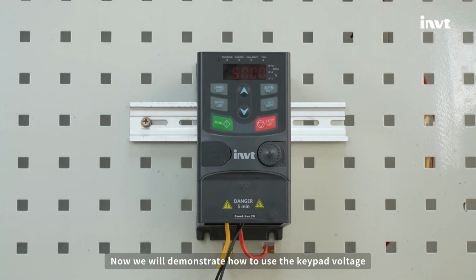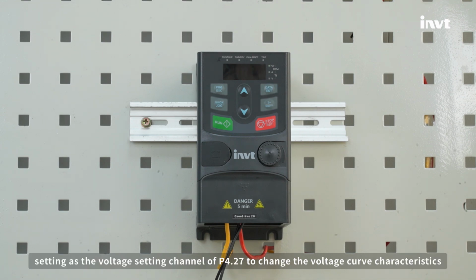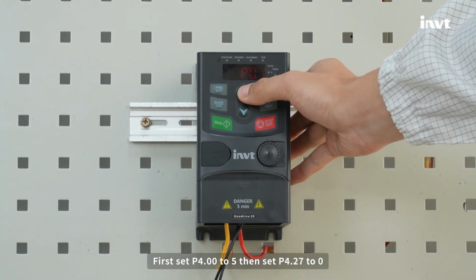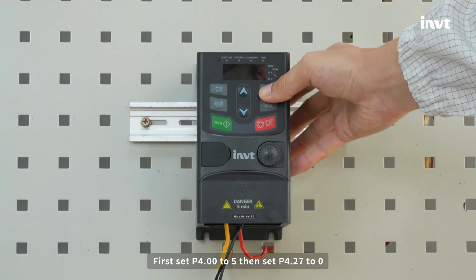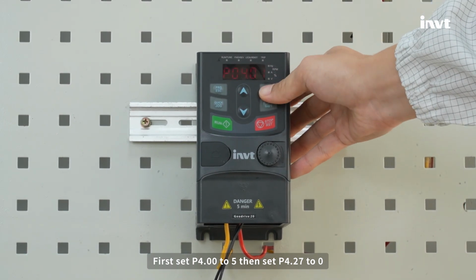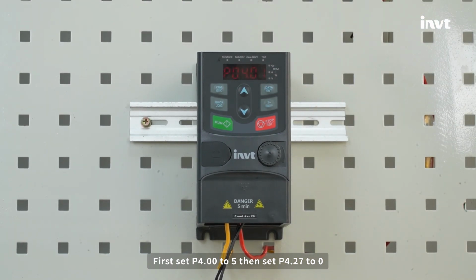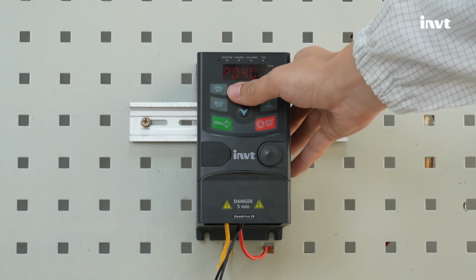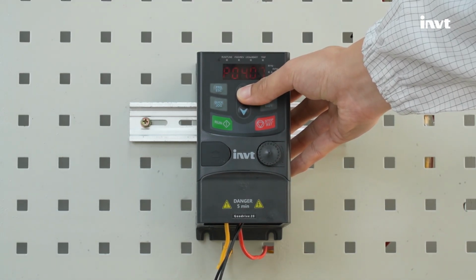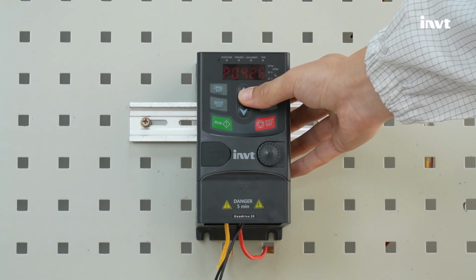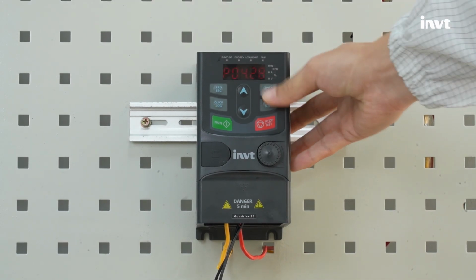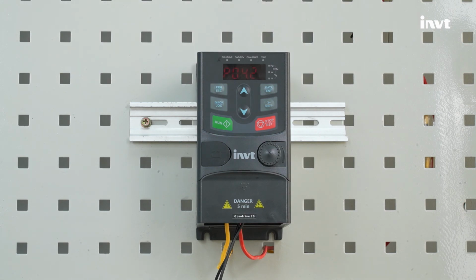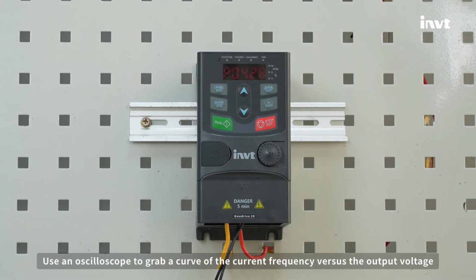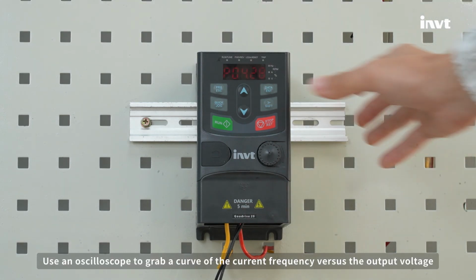Now, we will demonstrate how to use the keypad voltage setting as the voltage setting channel of P4.27 to change the voltage curve characteristics. First set P4.00 to 5. Then set P4.27 to 0. Use an oscilloscope to grab a curve of the current frequency versus the output voltage.